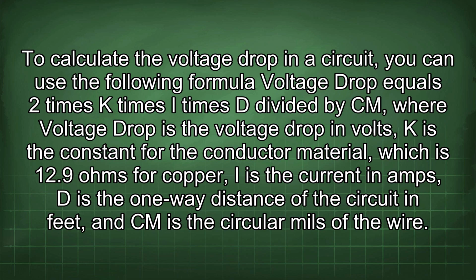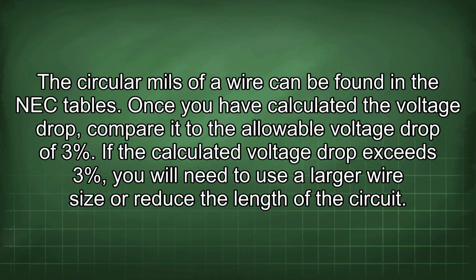To calculate the voltage drop in a circuit, you can use the following formula: voltage drop equals 2 times K times I times D divided by Cm, where voltage drop is the voltage drop in volts, K is the constant for the conductor material, which is 12.9 ohms for copper, I is the current in amps, D is the one-way distance of the circuit in feet, and Cm is the circular mils of the wire. The circular mils of a wire can be found in the NEC tables.